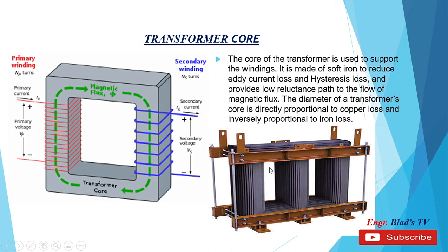Transformer core. The core of the transformer is used to support the windings. It is made of soft iron to reduce eddy current loss and hysteresis loss, and provides a low reluctance path to the flow of magnetic flux. The diameter of a transformer's core is directly proportional to copper loss and inversely proportional to iron loss. In this picture we can see a typical assembly of a transformer core, with a primary winding wound on the primary side and a secondary winding wound on the secondary side. Voltage applied from the primary will produce a magnetic flux through the core, and the amount of magnetic induction produced will induce a voltage in the secondary winding.